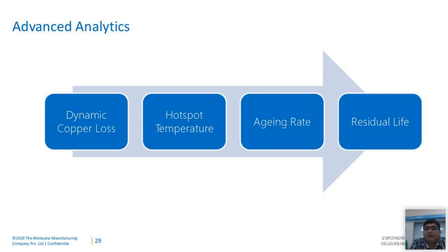There could be further techniques deployed in terms of offline testing, like furan analysis from oil, which can give you a more accurate picture. But this is an indicative expected life based on the thermal model, which essentially depends on the dynamic loading on the transformer as well as the persistence of hotspot temperature for a considerable amount of time. This sometimes occurs when transformers are loaded beyond capacity for a considerably long period of time, or there is some issue with the cooling circuit of the transformer.